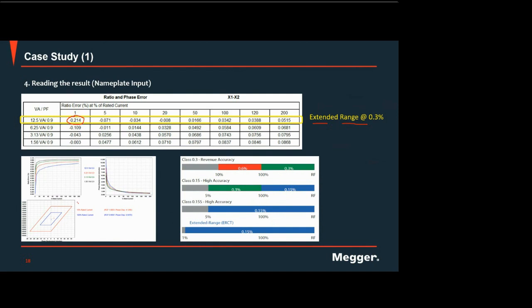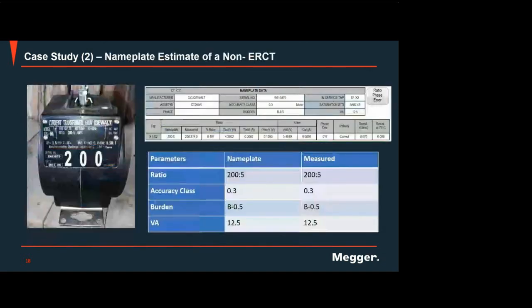And looking at the parallelogram for metering application, you can see that the value or the X are inside the box. So meaning to say, this is a very, very accurate CT here. Okay. Now, to check whether the MRCT is really displaying the correct values, we tried to test a non-ERCT, or not an extended range CT.